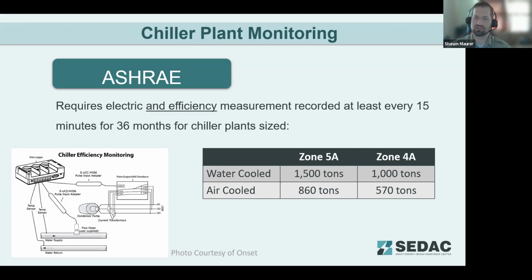ASHRAE also includes chiller plant monitoring. This is not something that's included in the IECC. I believe this may be something that's being added though. So it requires electric and efficiency measurements to be recorded every 15 minutes for a 36-month history at minimum, so that you can monitor the performance of your plant over time. The main thing they're looking at here is that without monitoring that data, you can't catch issues when they arise until it becomes a major concern. So this is looking at maintaining the long-term performance of building energy efficiency with its HVAC systems.